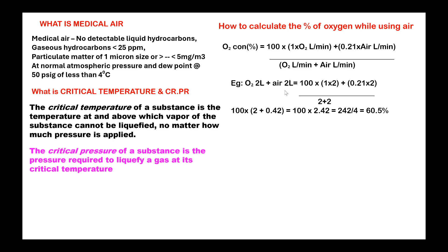Everything is given in the monitor itself. But the calculation you have to know is, supposing you use 2 liters of oxygen and 2 liters of air: oxygen has 100% oxygen, whereas air has only 21% oxygen. So for oxygen, 100 into 1 into 2, that is 100%. And for air, it is 0.21 into 2 liters, which becomes 0.42. The total volume is 2 plus 2, which is 4. Multiplying these out, you will get roughly 60.5% oxygen if you use 2 liters of oxygen and 2 liters of air. That is how the calculation is done.